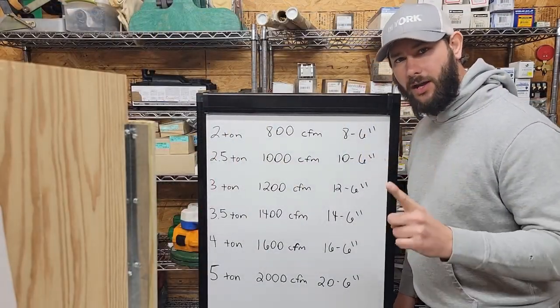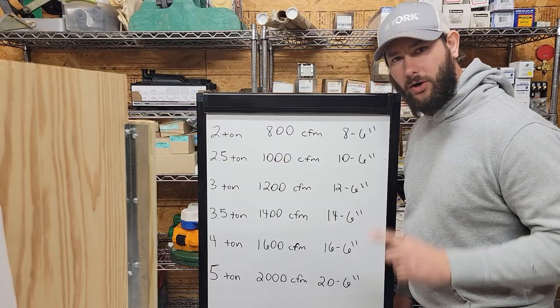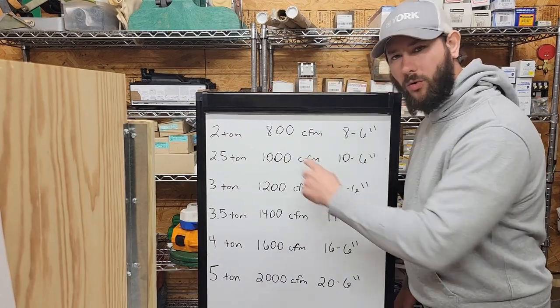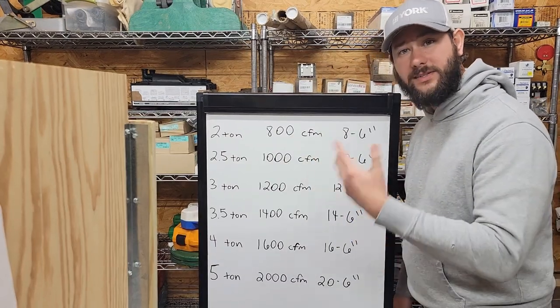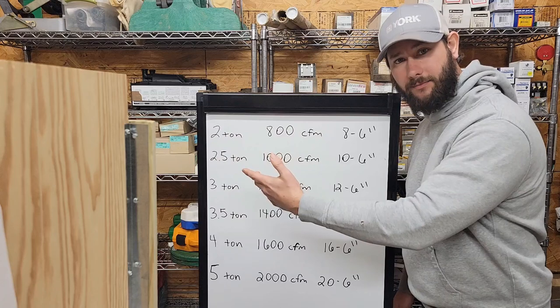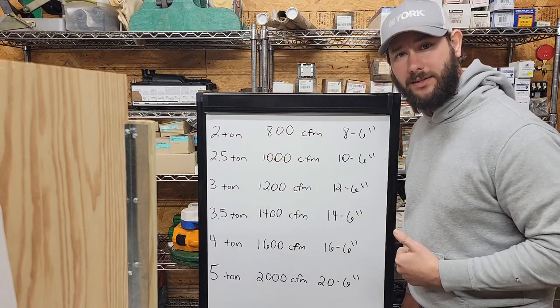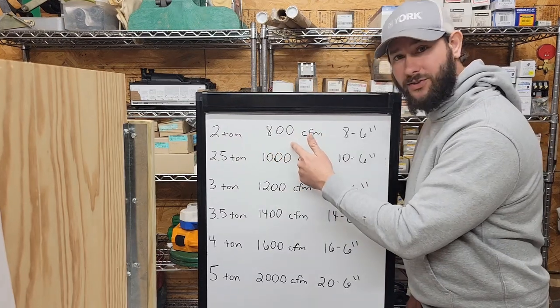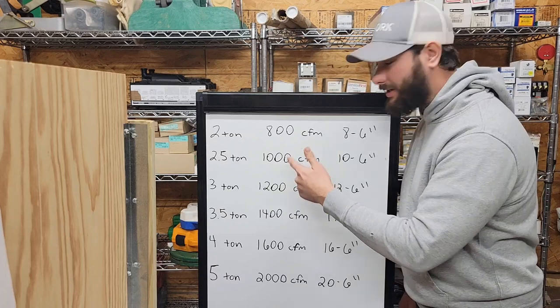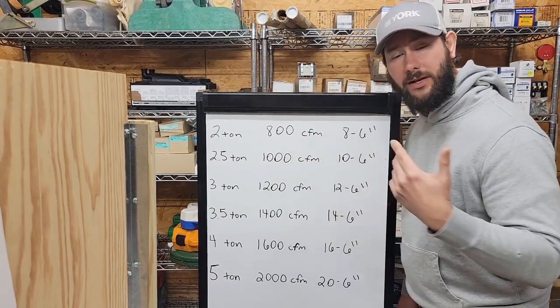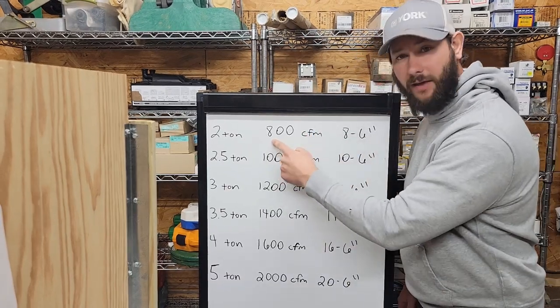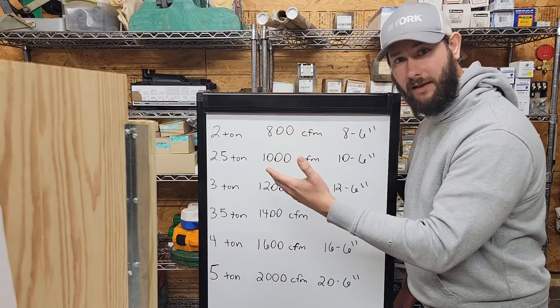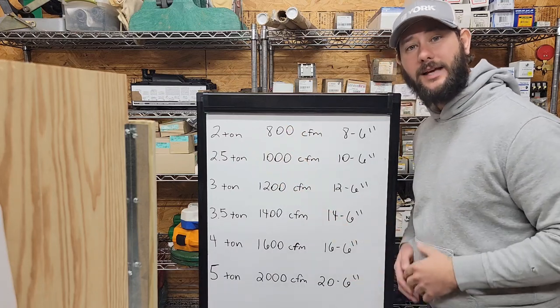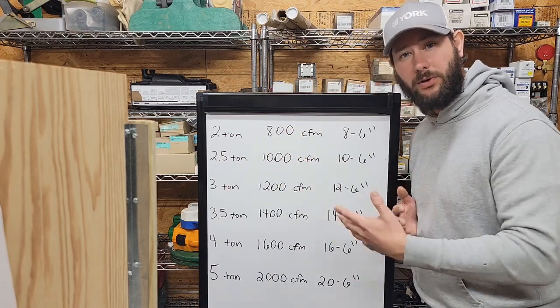First thing you need to know to be able to size ductwork properly is the total quantity of air, or the CFM, per ton. That's how you're going to get your first duct size. I'm going to get my first duct size for this 2-ton unit because I know that this 2-ton unit is rated for this amount of air, this air quantity, this CFM. And I get that because I'm using 400 CFM per ton.